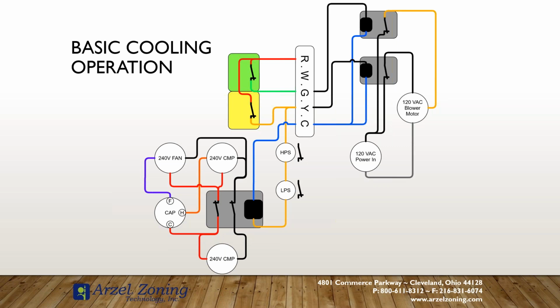And then they go to their outdoor unit, and while everything inside the voltage tests out great, there's no low voltage to control that contactor outside. And it almost always comes back to a high pressure or a low pressure switch is tripped. So that's why I have them drawn into here. Or potentially a mouse chewed on a wire, broke it. The dog chewed on a low voltage wire. That's a pretty common one as well. But it's a break in the wire somewhere. And if it's not a mouse or a dog or a cat or somebody with their weed trimmer getting too close to the air conditioner, it's probably the high pressure or the low pressure switch. So those have to be closed, and when they're closed, they allow the contactor to start. The contactor starts, brings on the fan and compressor at the same time.